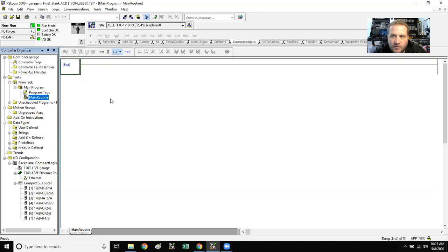It doesn't have to be a formula. You should be able to just get it wrapped around your brain. Like, oh, I need to take this and turn it into a percentage and apply it to that. To make it into a percentage, we just take our input minus the low number divided by the range of numbers. Yeah. And then we can apply that to whatever we want.